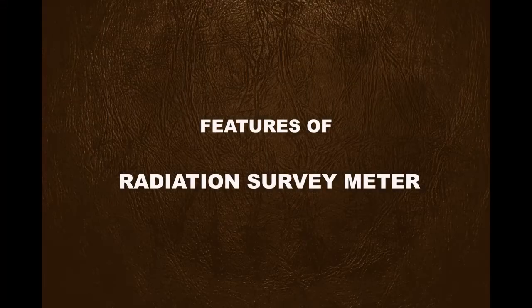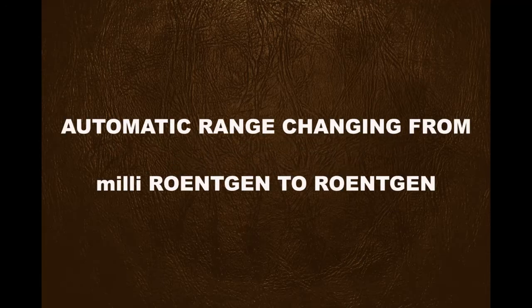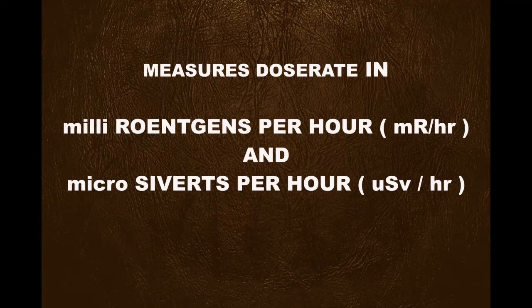Some important features of this machine are: 1. Compact, elegant, and light in weight. 2. Automatic range change from milli-roentgen to roentgen. 3. Measures dose rate in milli-roentgen per hour and micro-sieverts per hour.